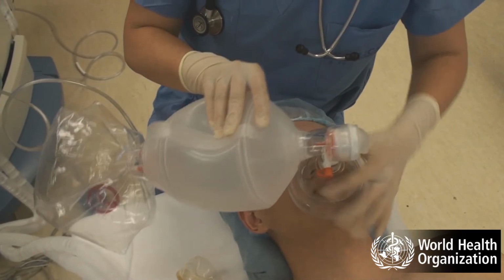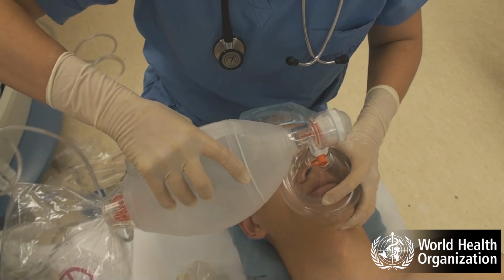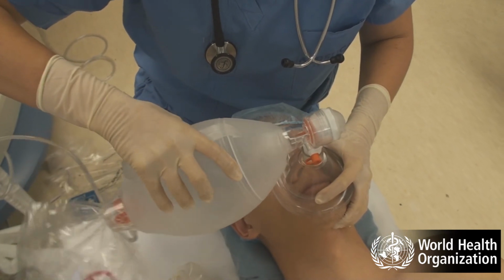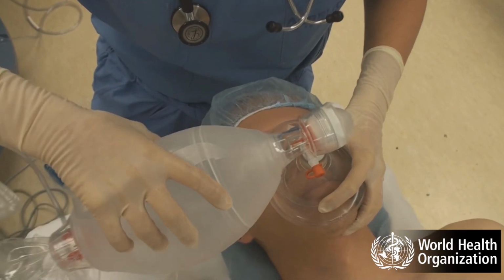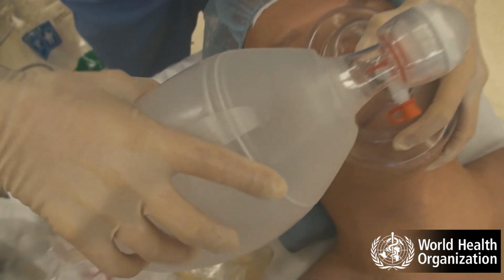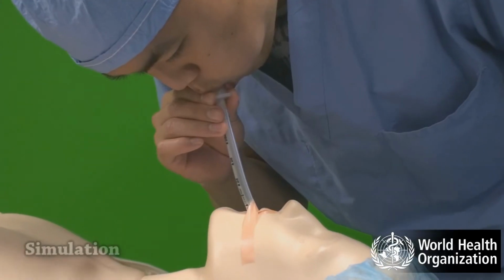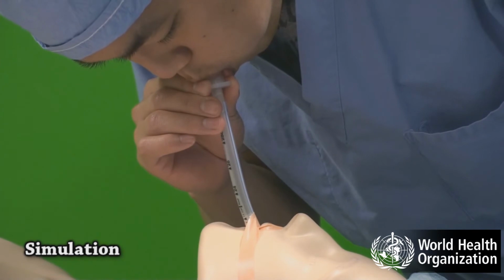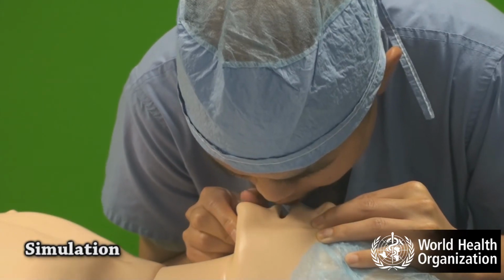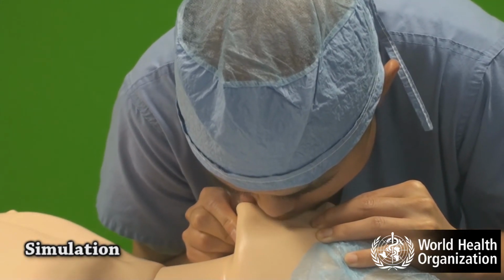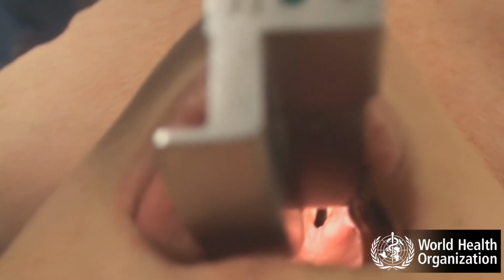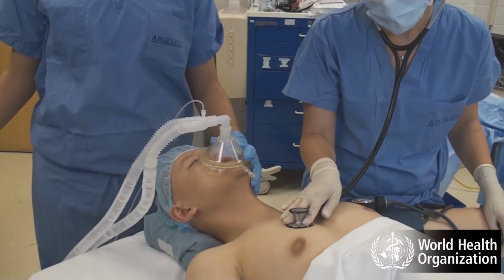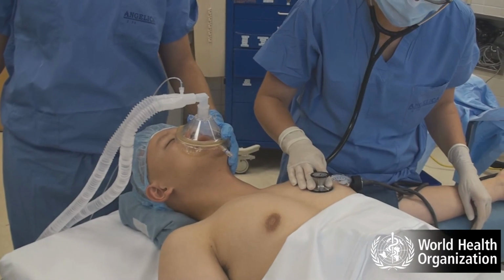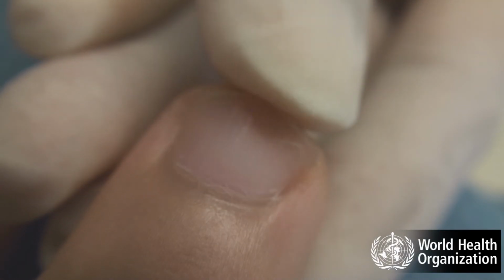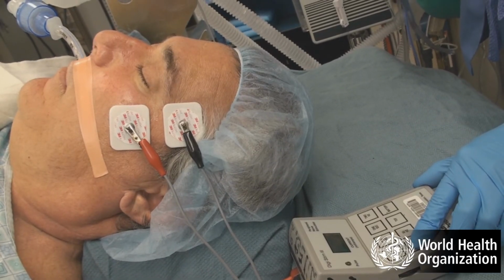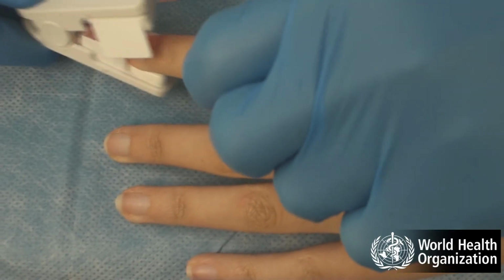If it is felt that the anesthesia equipment is faulty, use a self-inflating bag to ventilate the patient with air while new equipment or oxygen supplies are obtained. If equipment is missing, mouth-to-tracheal tube or mouth-to-mouth ventilation may be life-saving. It is important to treat each element of the sequence in order. After going through A, B, C, D, E, recheck them until the patient's condition has improved.